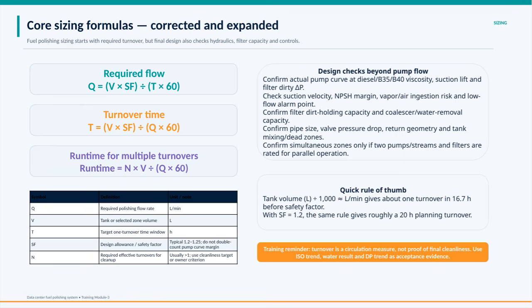However, sizing doesn't stop at pump flow calculations. You need to verify the actual pump curve under real conditions, considering fuel viscosity variations, suction lift, and filter differential pressure when dirty. Check suction velocity. Ensure you have adequate NPSH margin to avoid cavitation. Watch for vapor or air ingestion risks, and set appropriate low-flow alarms.